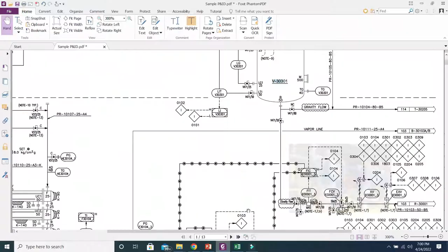So here you can see DCS mentioned in place of system for each and every tag. But few instruments do not have the IO type and also do not have the system, just like local instruments. So what are the local instruments? Any non-electronic items which are not used to provide the signals, just like pressure gauge, temperature gauge, pressure safety valve, regulating valve, level gauges. These are the local indication items. So for these items we will keep blank IO type and system both.